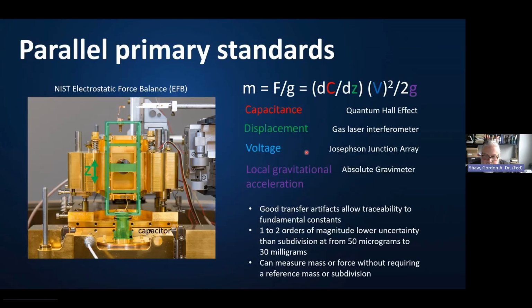The way that this balance works, I have a picture on the left here. I have highlighted in green the moving part of the balance mechanism, and on top is our mass pan. This is where a calibrated mass would be placed, or another force that we would like to generate. We compare the weight of this mass to the electrostatic force generated at a capacitor down here at the bottom of this moving part of the balance.